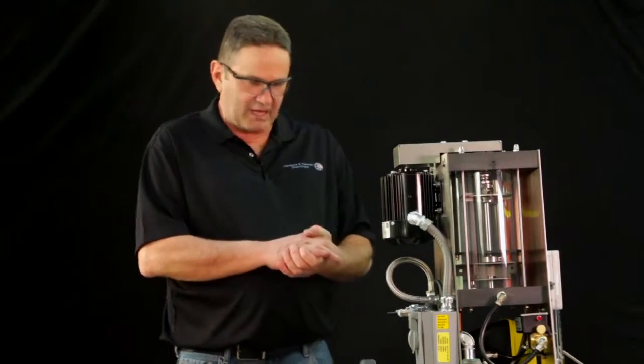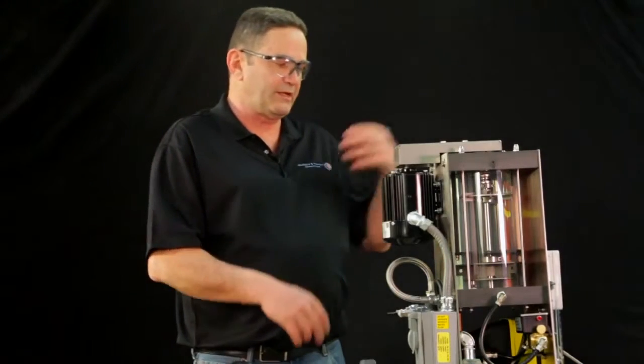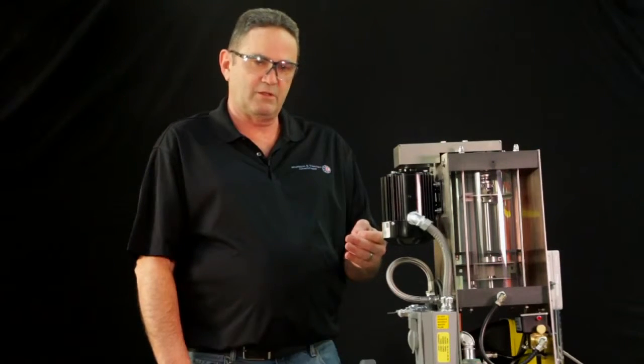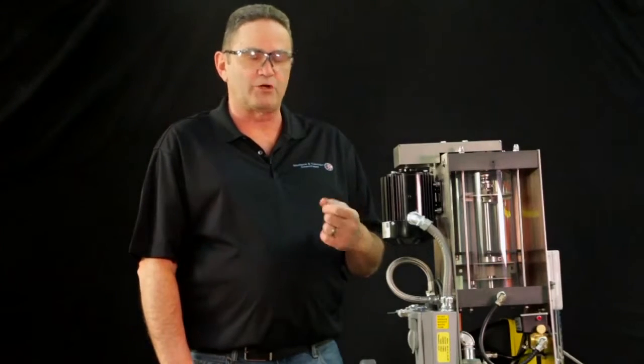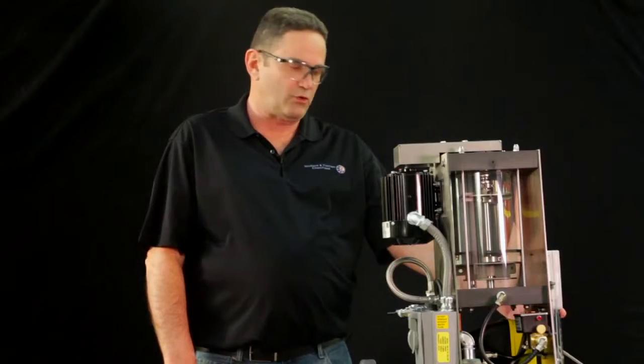Another is the polymer pump is not working. The common cause of your polymer pump not working is your controller. Is it in external and you're trying to run it internally? Or is it in external looking for that 4 to 20 milliamp signal and you've lost your 4 to 20 milliamp signal? The other one could be on the faceplate, you have an internal-external switch located on the pump face itself. Did somebody turn that from external to internal? Another thing that I would normally check, and I would always recommend, ensure that your cables are securely fastened. That's the majority of the reasons.